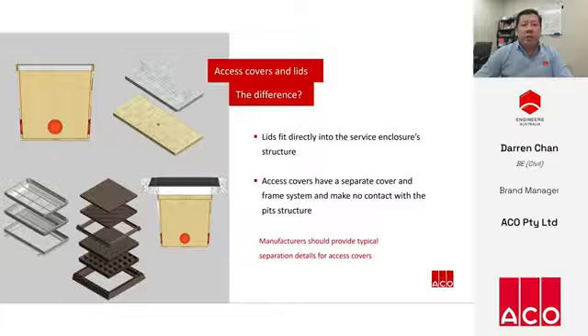A lid is positioned directly into the pit rebate, so any loading applied to the lid is supported by the pit. A lid is only available for light to medium loads, as the load is transferred directly to the pit walls. Access covers, on the other hand, comprise a separate cover and frame. The frame is supported by the pavement or slab, allowing the load to be transferred away from the pit. This is why access covers are used for heavy-duty applications. And to help with the design and integration of the cover into the pavement, manufacturers should provide typical separation dimensions between the pit and the access cover for different load scenarios.